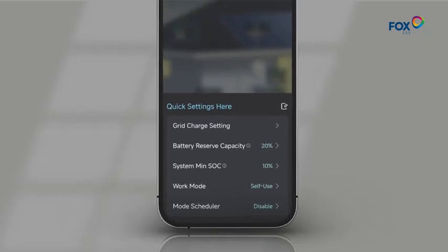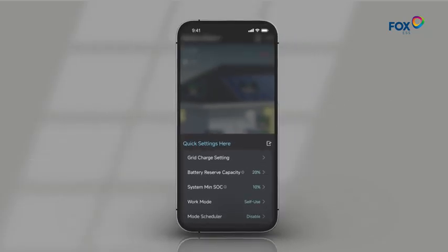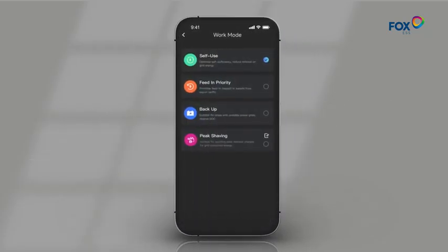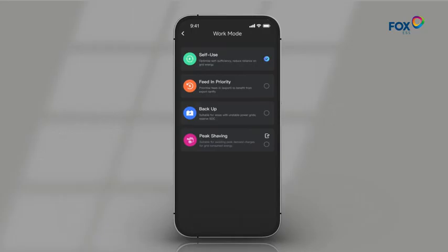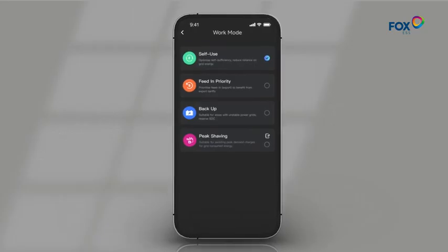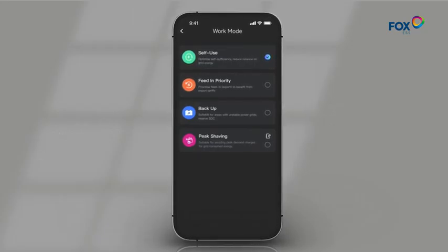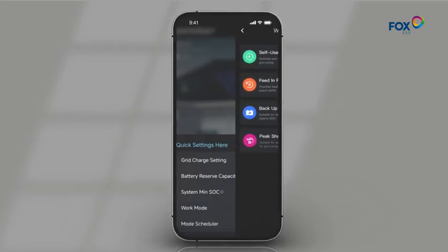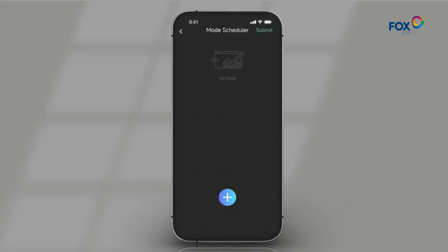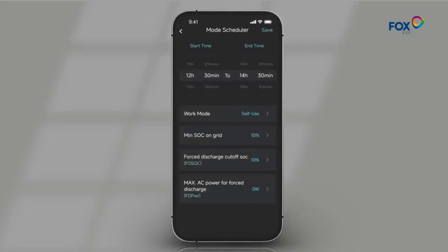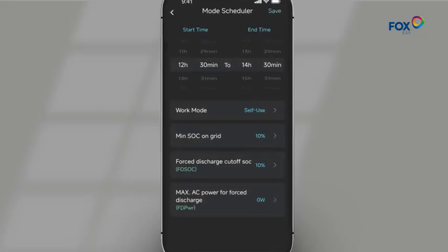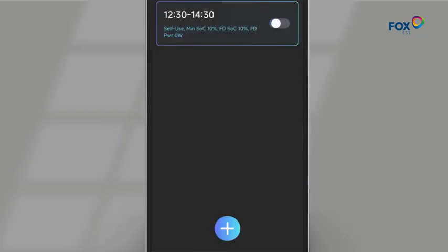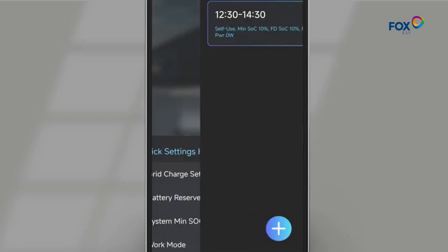You can choose to set the work mode to self-use or feed in priority, and available work modes may differ between inverter models. You can automatically switch between work modes throughout the day using the Mode Scheduler. The Mode Scheduler allows for more advanced charge-discharge scheduling.